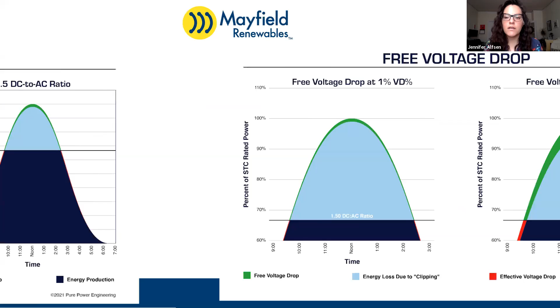Yeah, so I think that's a question that comes up a fair amount. It used to come up a lot. And, as Rick was talking about the DC voltage drop, you have a lot more flexibility with being able to run the DC conductors a further distance. And a big part of it is most of our systems are going to be, in a ground mount system, utilizing 1500 volt inverters, 1500 volt arrays. And so your voltage is already much higher than what the output of the inverter is going to be, either at 600 volts or 480 volts.